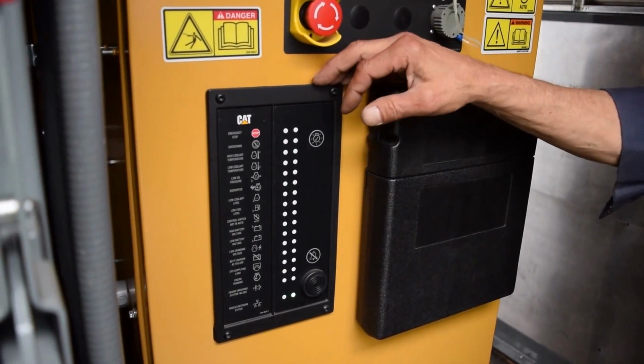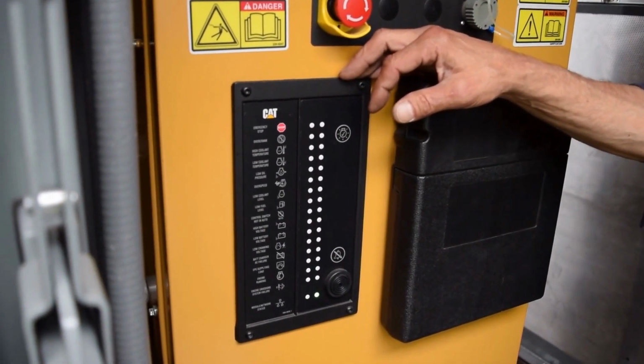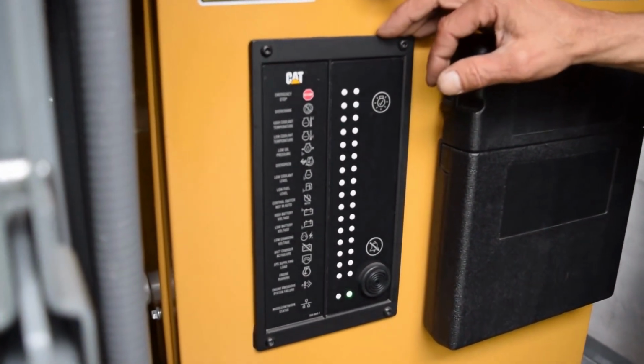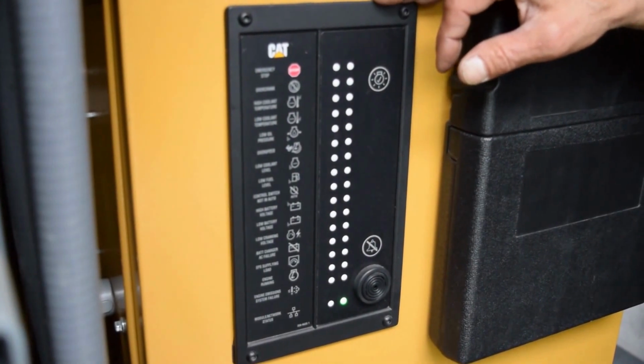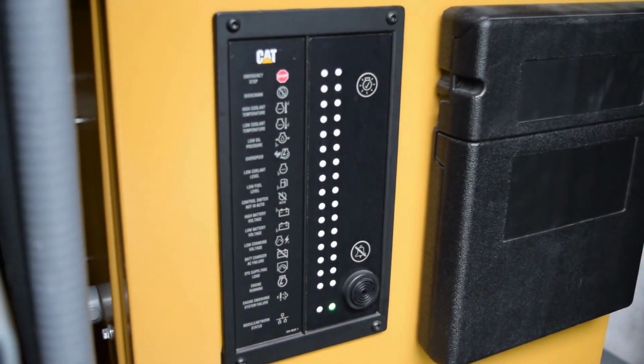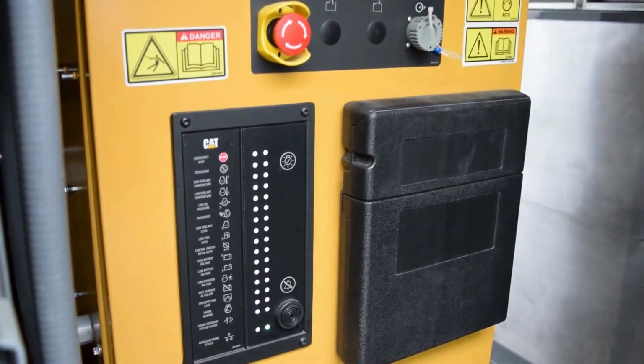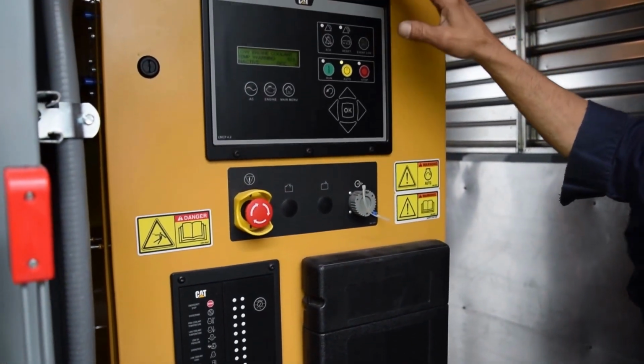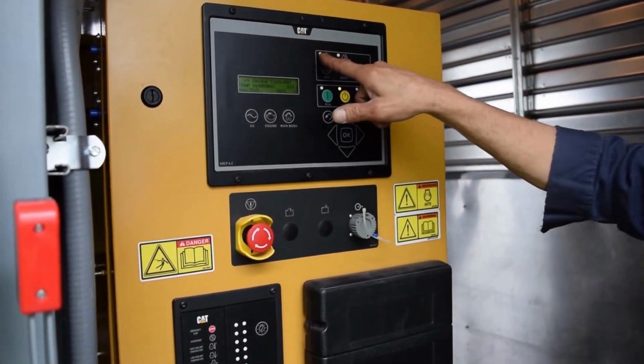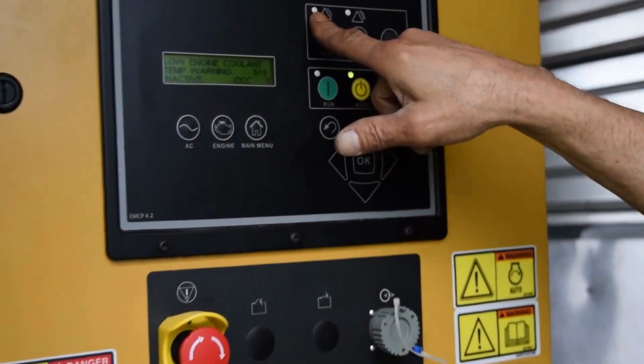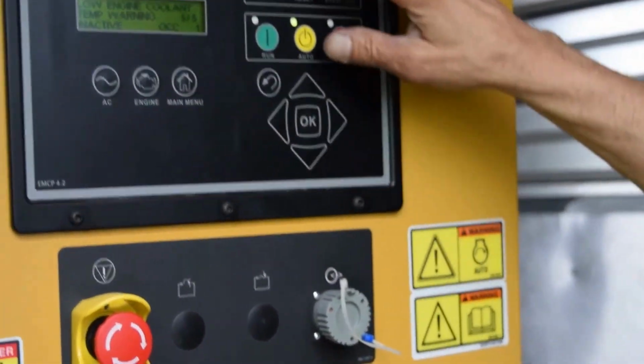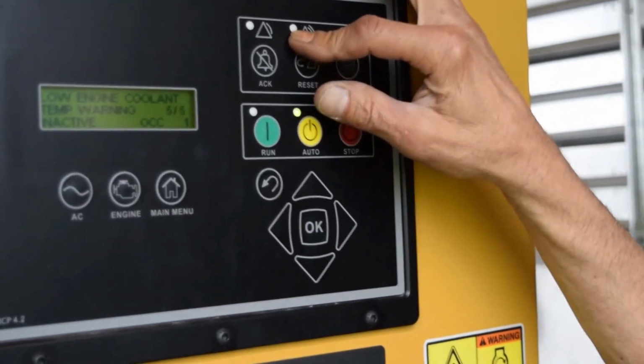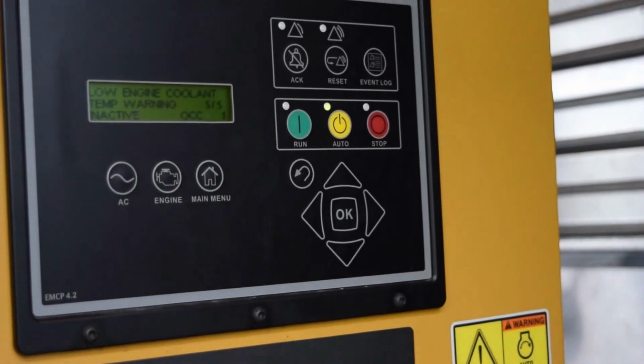They are not wired lights, it runs on RS-485 data. And you can put almost as many of those as you want in the system. With that being said, when you get a warning, the amber light here will flash to tell you you've got a warning, and if you get a shutdown, the red light will light up to give you a shutdown.